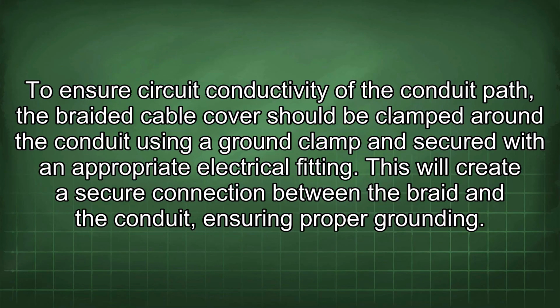To ensure circuit conductivity of the conduit path, the braided cable cover should be clamped around the conduit using a ground clamp and secured with an appropriate electrical fitting. This will create a secure connection between the braid and the conduit, ensuring proper grounding.